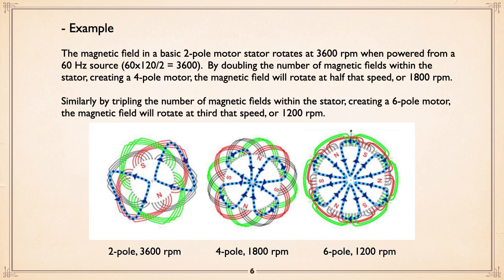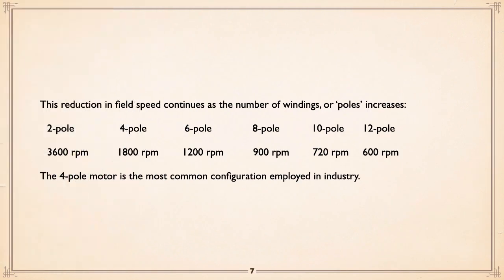Now, for example, you can see in these three, if you've got two poles, 3,600 RPM, the magnetic fields are rotating at 3,600 RPM. 4-pole, they're rotating at 1,800. 6-pole, they're rotating at 1,200. And so a 2-pole synchronous speed is 3,600. 4-pole, you can follow. It goes beyond 12-pole if you really want, but that's about as far as we normally would see it go. By far the most common speed in industry is the 4-pole motor, 1,800 RPM synchronous.